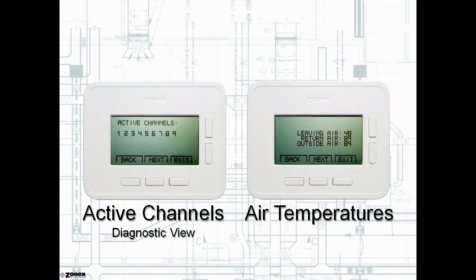From the monitor menu, you can select a system diagnostic that will provide a listing of dampers that are wired properly and communicating with the system. This is a huge time saver for the contractor looking for an easy way to confirm wiring operation. And if a wiring error did exist, it quickly identifies where it's located, saving hours or days wringing out the wiring. The second diagnostic screen provides critical operating data, including the leaving air temperature from the unit, return air, and outside air temperatures.